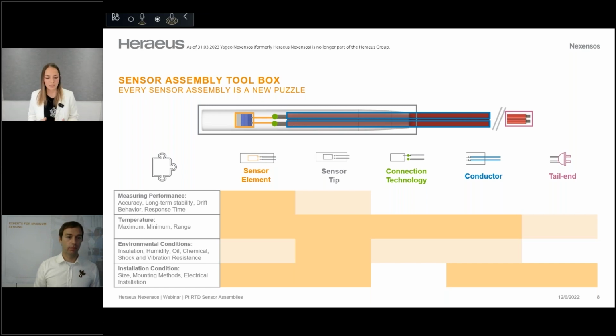And last but not least, the sensor assembly needs to be installed, and therefore it's very decisive when it comes to size, to mounting methods, and also to the electrical installation. Talking about the size, the main influence is the sensor element and the sensor tip. And sometimes the customer wants to have an easy installation of the sensor assembly. For example, he wants to simply screw it in, plug it in, or glue it in, or whatsoever. Then we need to adapt the sensor tip in terms of those mounting requirements. And the conductor and the tail end are decisive for the electrical installation. The conductor, for example, when it comes to the length of the conductor, and for the tail end, the plug could be really customer specific.